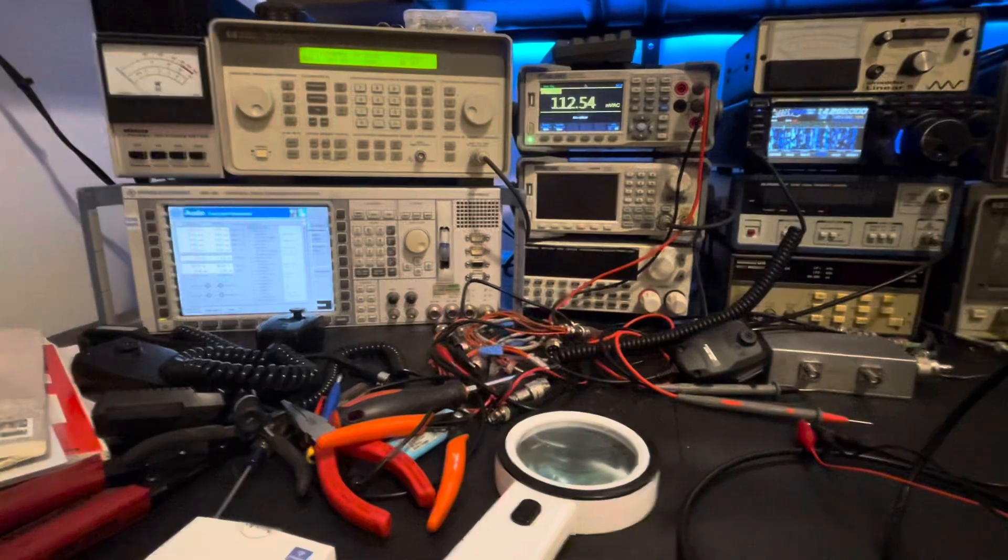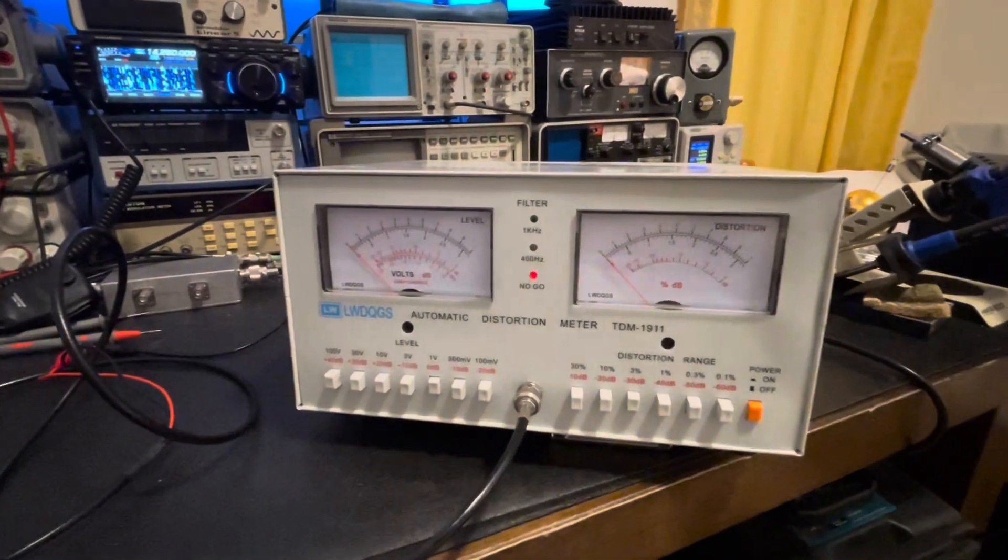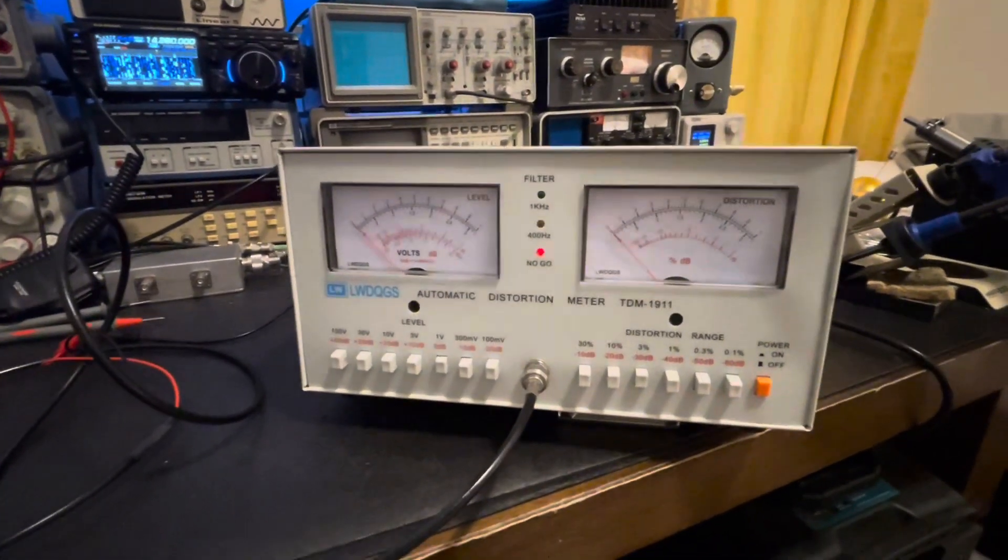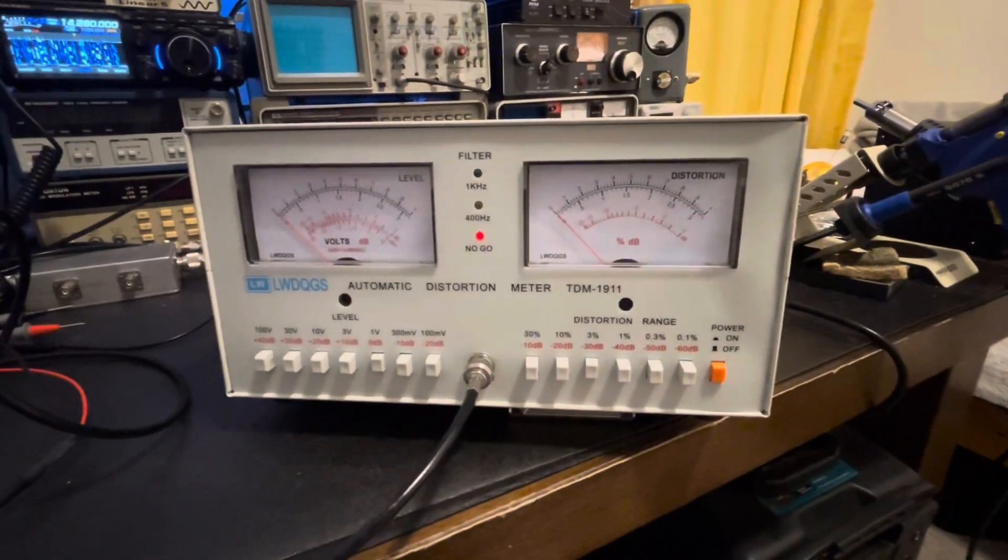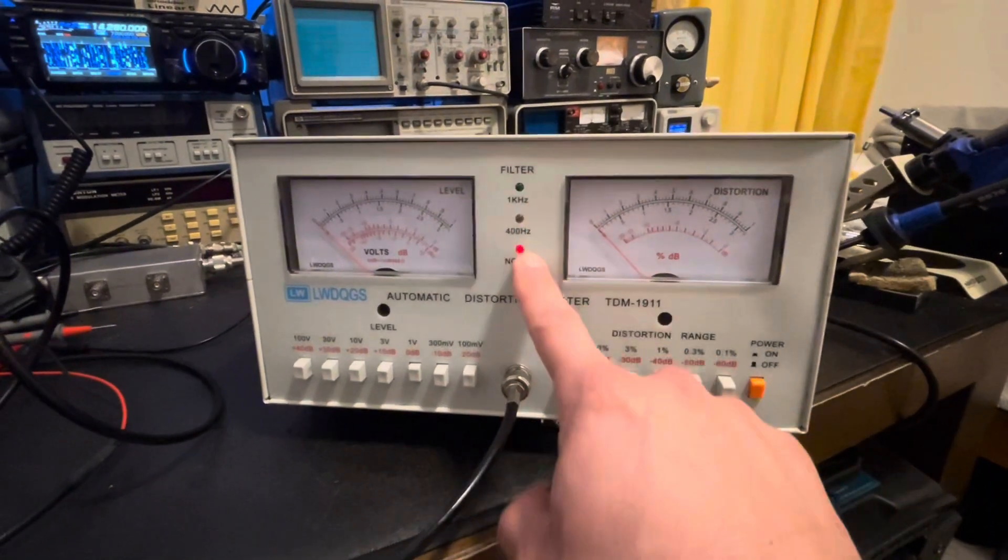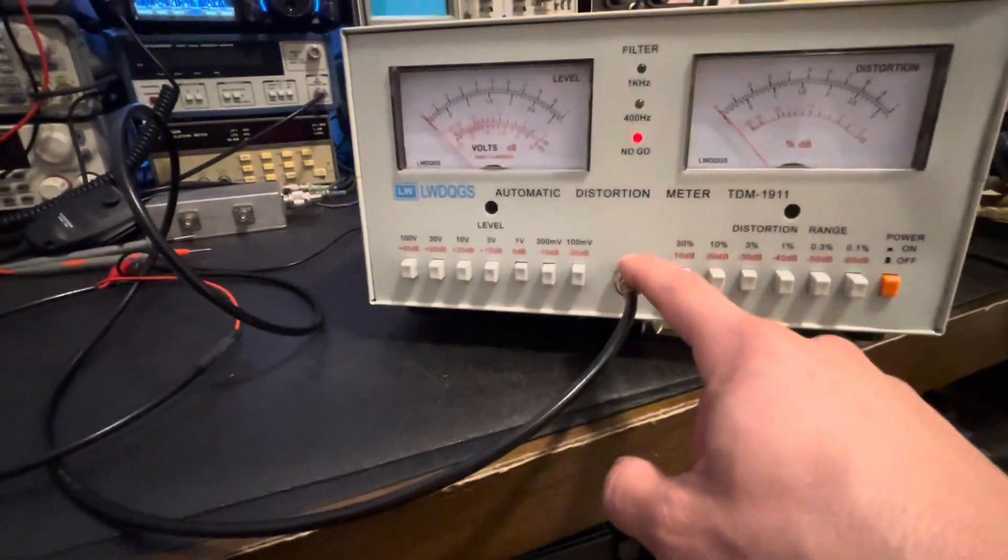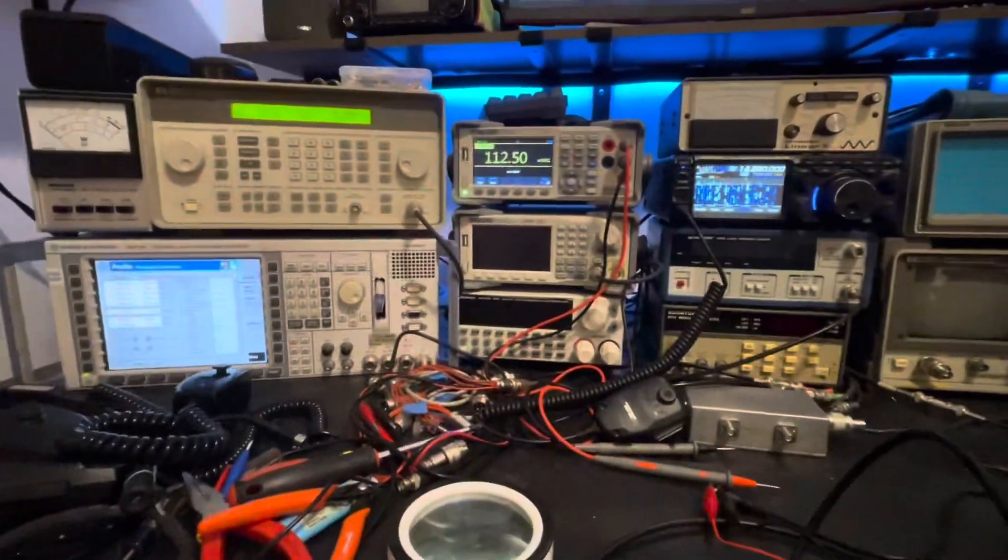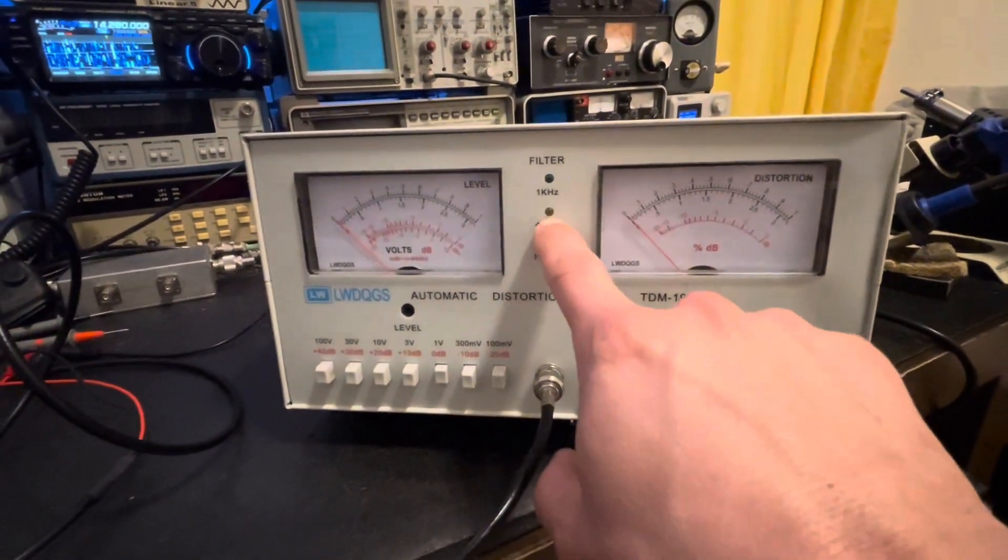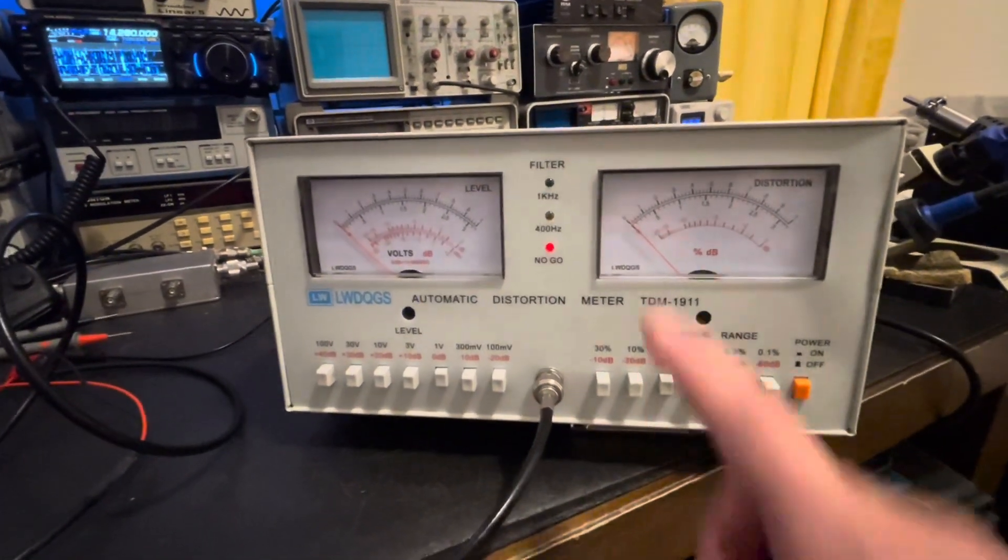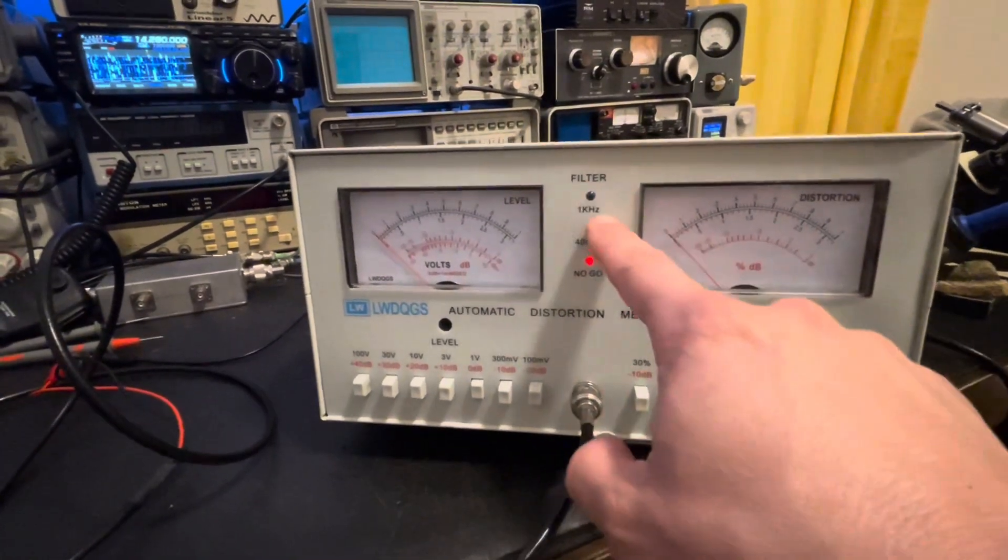Looking at this thing, we've got just a basic on-off power button and we have three LEDs on the front. This one down here is illuminated right now, it just says no-go because we have no signal input at this point. My generator is off so we've got no output out of the radio. We do have a 400 hertz LED and we have a one kilohertz LED there that'll illuminate when it detects one of those two frequency inputs.